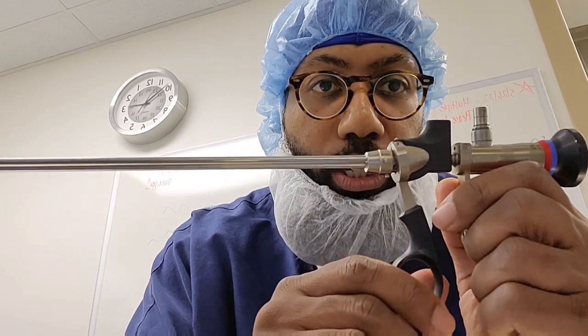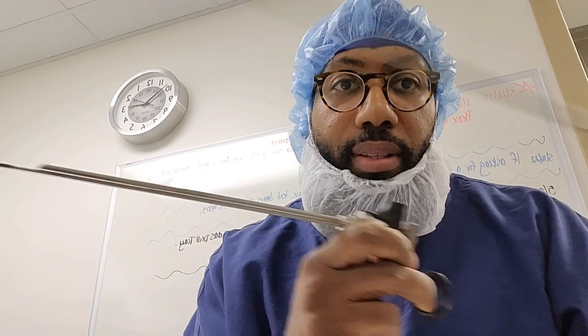Let's go to the next one. I have another one for you guys. This one is common, happens a lot at different hospitals, mainly because of the training systems that a lot of people fail to get, or the leadership or senior people aren't passing information down. So usually you'll get a cysto tray — it's supposed to come broken down from the OR and then come down here. What happens is when it comes down like this and you get it in the washer like this, you should know that something is wrong, because this is not supposed to be in there.